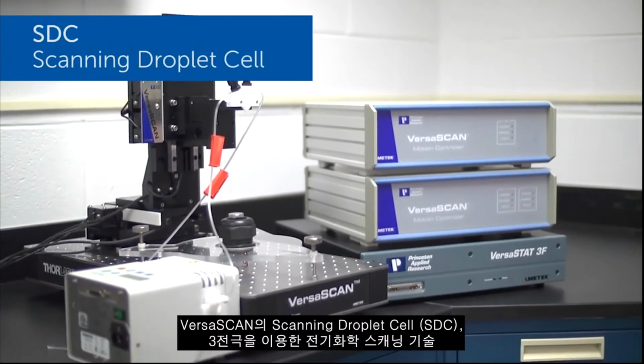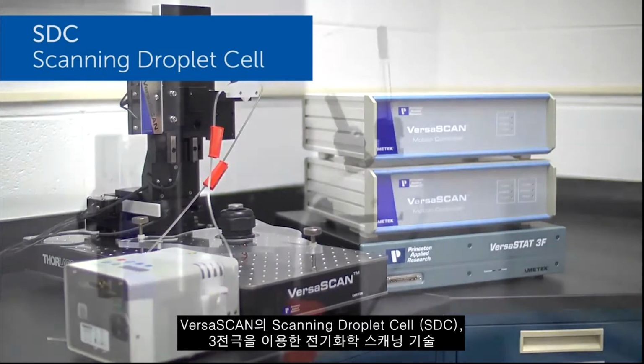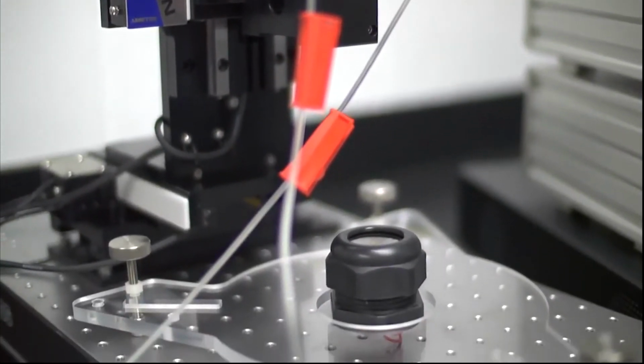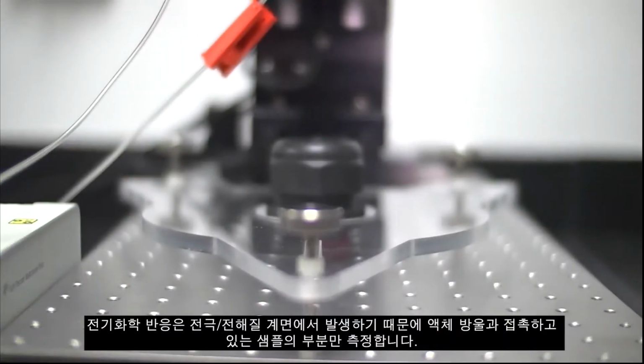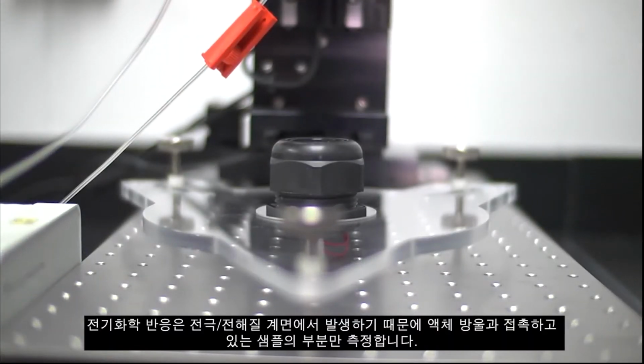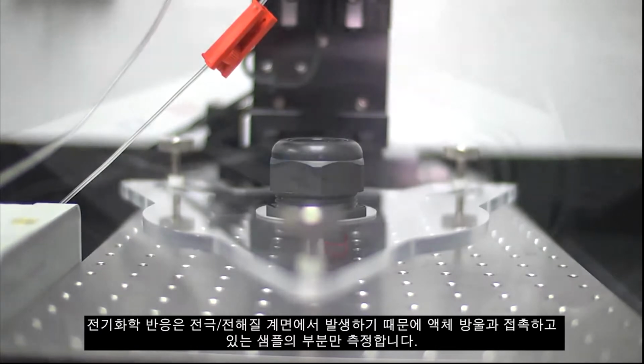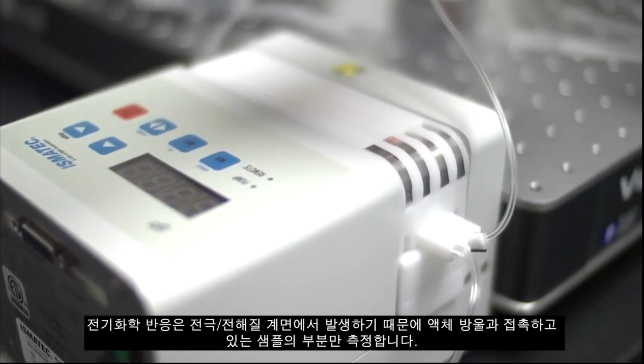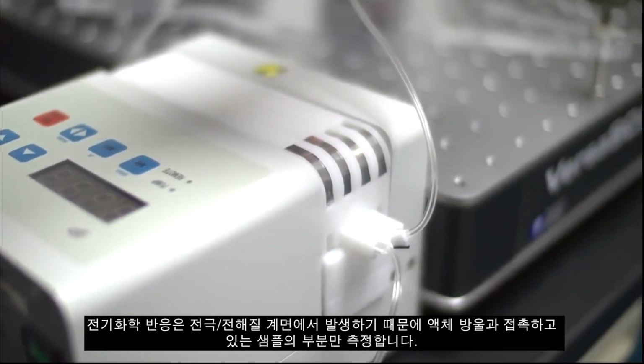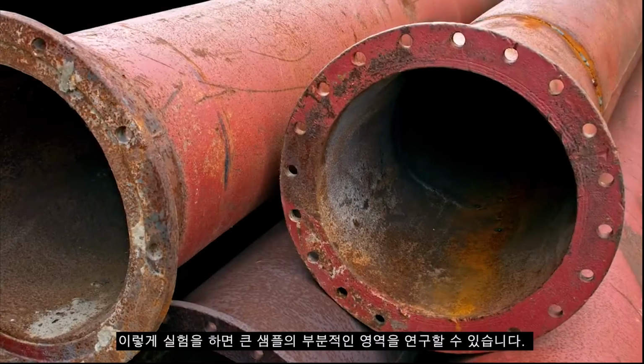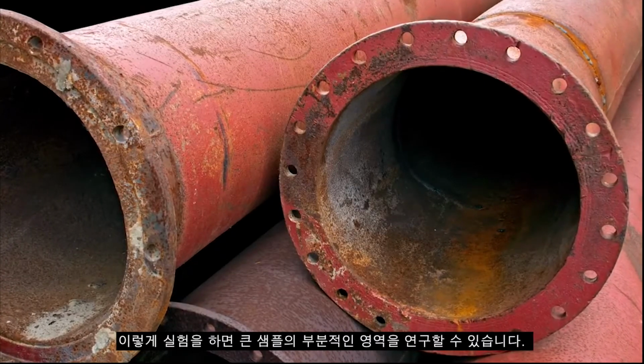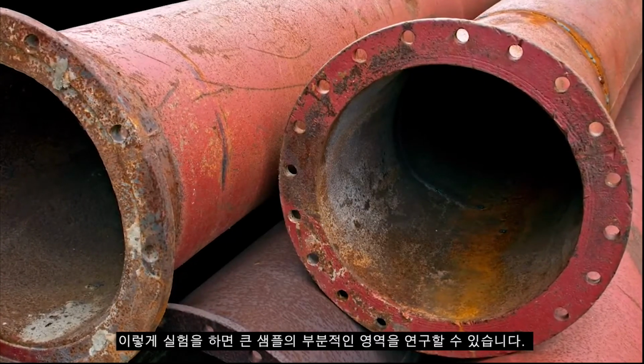The VersaSCAN Scanning Droplet Cell, or SDC, is a traditional 3-electrode experiment with a localized electrochemical cell scanned across the surface of a sample. Since electrochemistry occurs at an electrode-electrolyte interface, only the portion of the sample that is in contact with the droplet is being measured. This allows experiments to study a small area of a large sample. SDC experiments can be configured in one of two ways.